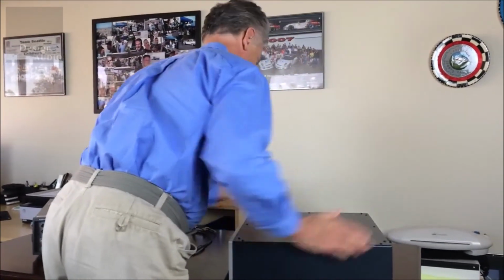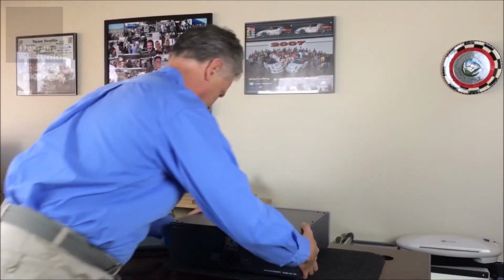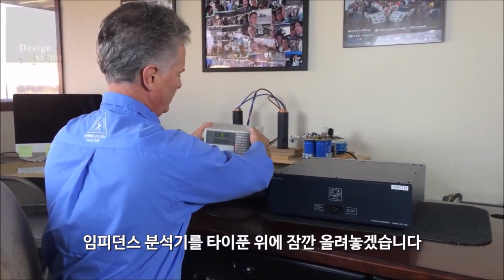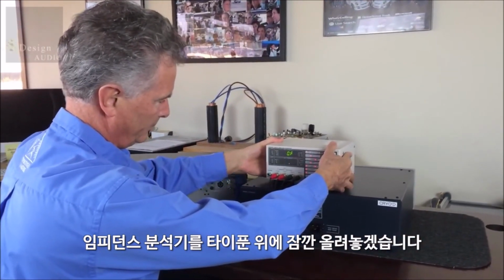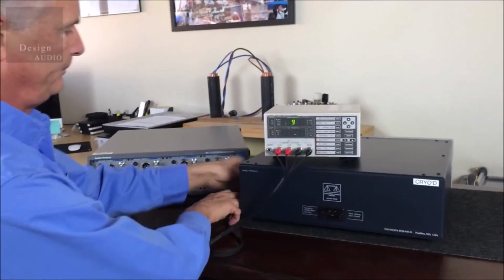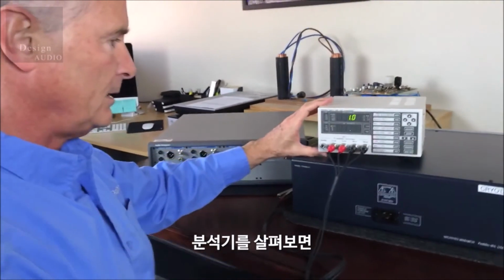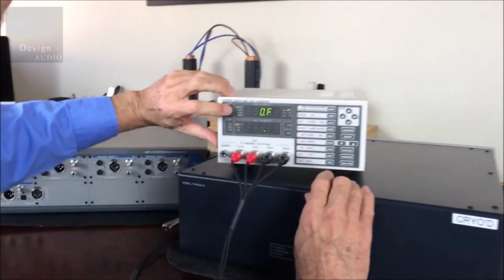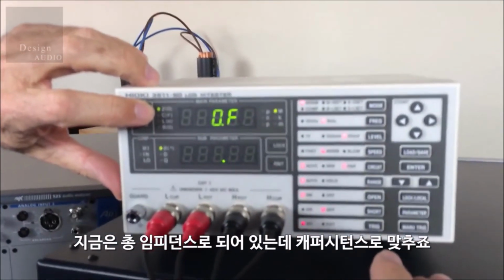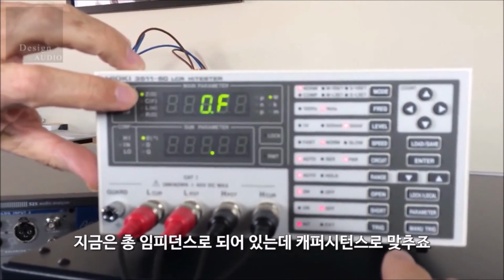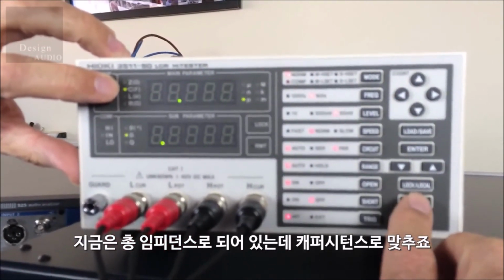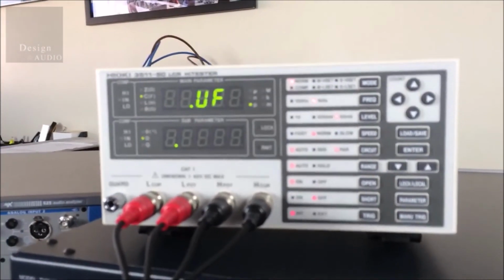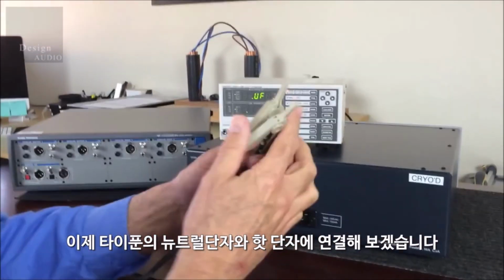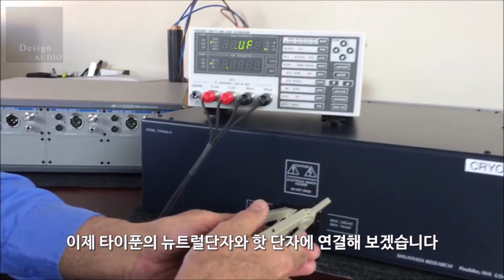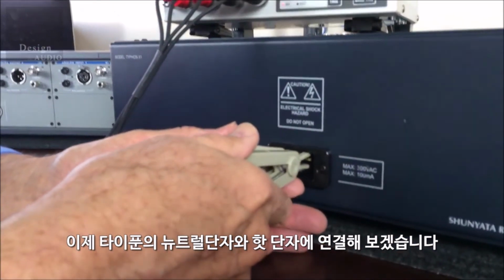I'm going to turn the Typhon around so we can access the port on the back. And let's just move the impedance analyzer, put it right up on top of the Typhon so that you guys can see it easily. So let's zoom in a little bit here, and you'll see on this menu, right now it's set for total impedance, and we're going to set it for capacitance. And now we're going to take the probes and we're going to connect them to the neutral and the hot of the Typhon so that we can get a reading.